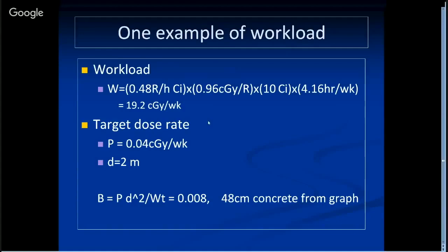Now I want the target dose rate at the control area to not exceed 0.04 centigray per week, but the point of interest is 2 meters away from your source. You can do the calculation and get that.